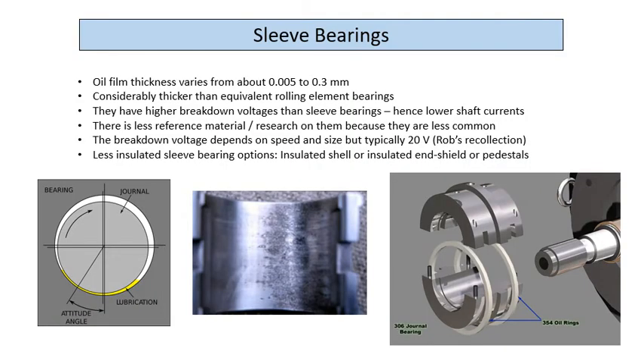Sleeve bearings, the oil film thickness, also, it really depends on whether you're talking about a bearing this big or a bearing this big, and you're talking about 100 RPM or 6,000 RPM. A 6,000 RPM machine of a decent size can have an oil film exceeding 0.5 millimeter. So the breakdown voltage that I found, the lowest one was about 20 volts. I see Troy's got some better things, and that's just a recollection. I couldn't find a similar thing recently on sleeve bearings, but generally they are much more resilient to shaft voltages.